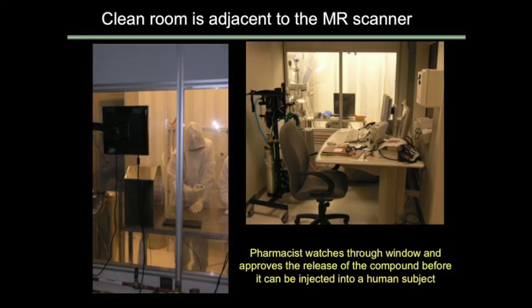We also checked the color, because the electron donor needed to be removed. There's a C18 column that filters out the electron donor, which happens to be green, so you can see it fairly easily, and we end up with a colorless compound to inject into the individual. This all has to happen within about 20 seconds, and then there are four green lights that go on. The person watching those lights says yes — it's okay to inject. If any light comes up red, it was not possible to inject.